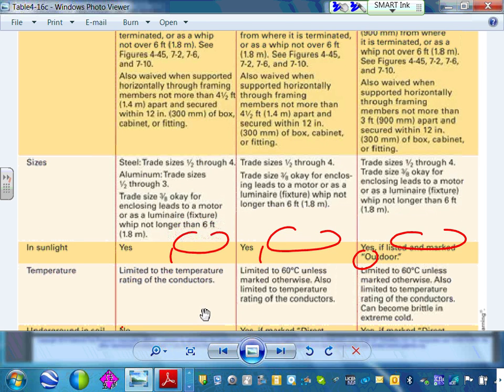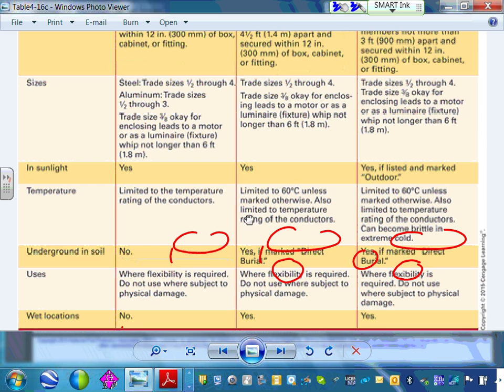Temperature. Remember, there's something called temperature limitation. Does this guy have one? Anything metallic, don't worry about temperature limitation. Put anything non-metallic and you're going to wonder at what temperature it's going to melt. It takes a lot of heat to melt this steel, but PVC, yes - you have to worry about 60 degrees Celsius. That's hot, guys. That's burning, man.